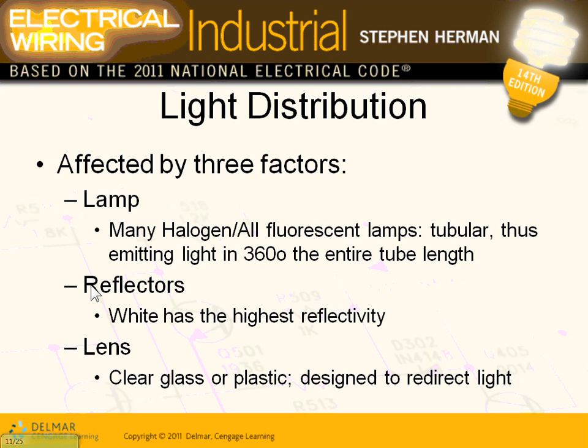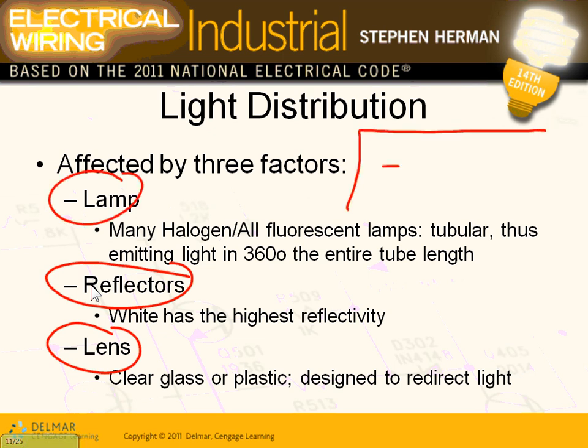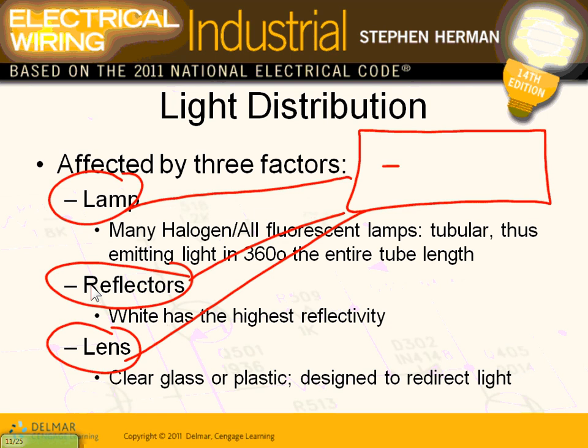The fixture that we use is LEDs. When you put lamps to make a lighting fixture — a luminaire — you need a lamp, you need a frame to put the lamp into, you need the ballast, you need a reflector to reflect the light in the right location, and you need lenses that distribute the light evenly so you don't see things very bright or very dark. These are all the parts of the luminaire. For a luminaire to exist you need a lamp, a reflector, lenses, a frame to protect the lamps and ballast, and the junction box for power.